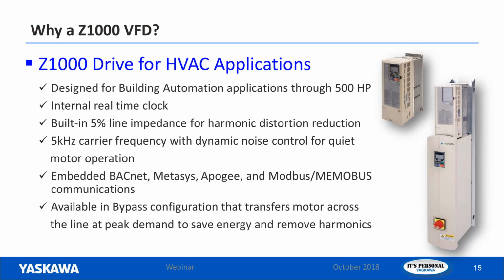So on its own, it can flip over into bypass, and now you're removing the drive and any potential losses you have in the drive, not to mention harmonic distortion that the drive would be adding into the system, and you're just running right across the line with the motor. Zero harmonic distortion now. Motor is a linear load. And the drive will still be monitoring the demand and call. So if the call or demand requires it to lower the speed again, it'll flip right back over into drive, and it's a seamless transition. You don't see a bump in the motor or anything, and it'll take over again.